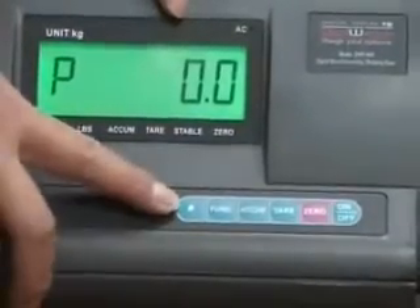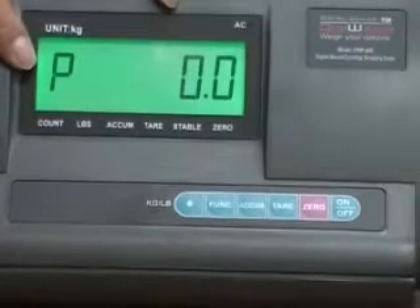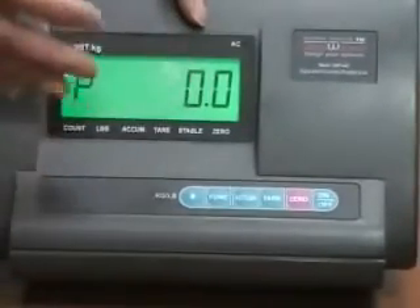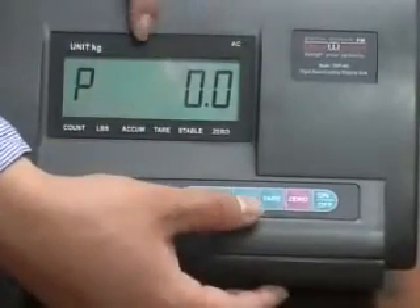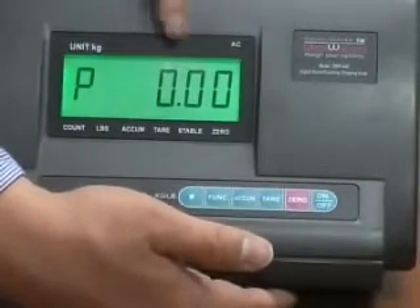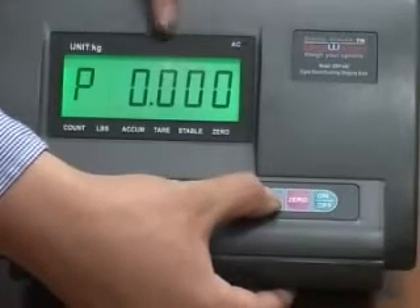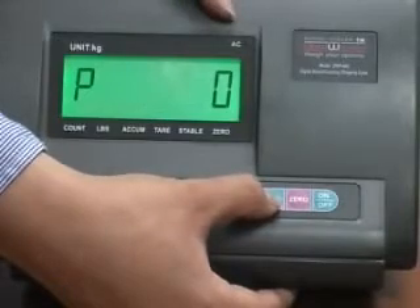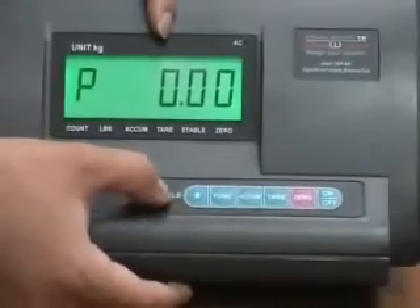Press the pound key to confirm and go to the next parameter. P means decimal. In this case, it shows one decimal, but for this scale we're going to change it to two. Press the tare key to change the parameter — now we have two decimals. You can press again for three decimals. When you find the correct one, press the pound key to confirm.